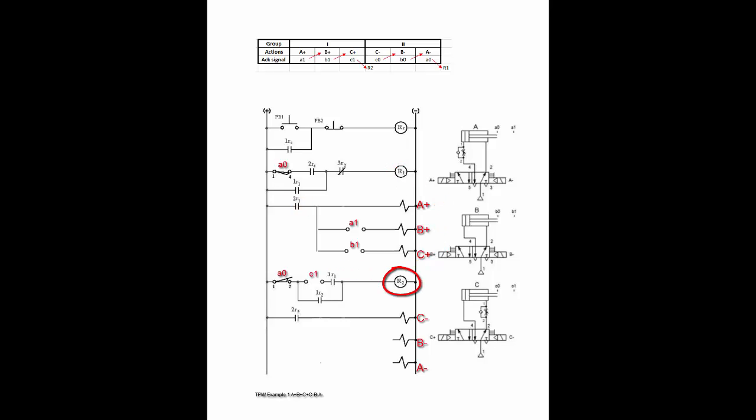Let us look at all the actions in group 2 under the control of group control relay R2. When R2 is on, contact 2R2 is closed. Since C minus is the first action in this group, C minus is activated immediately without going through any limit switch. When C minus is completed, C0 is activated. C0 triggers B minus. When B minus is completed, B0 is activated. B0 triggers A minus. When A minus is completed, A0 limit switch is activated. Since A minus is the last action in this group, two pairs of contacts in the A0 limit switch are used: the A0 1-2 pair is used to turn off R2, and the A0 1-4 pair is used to turn on R1 again.